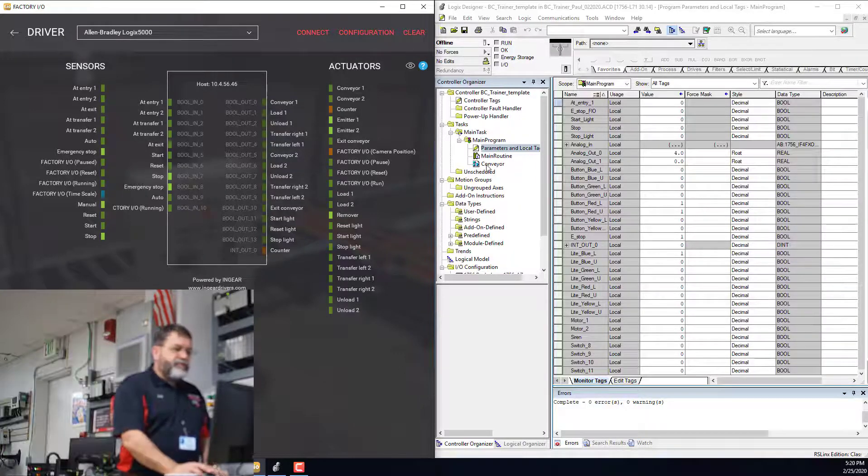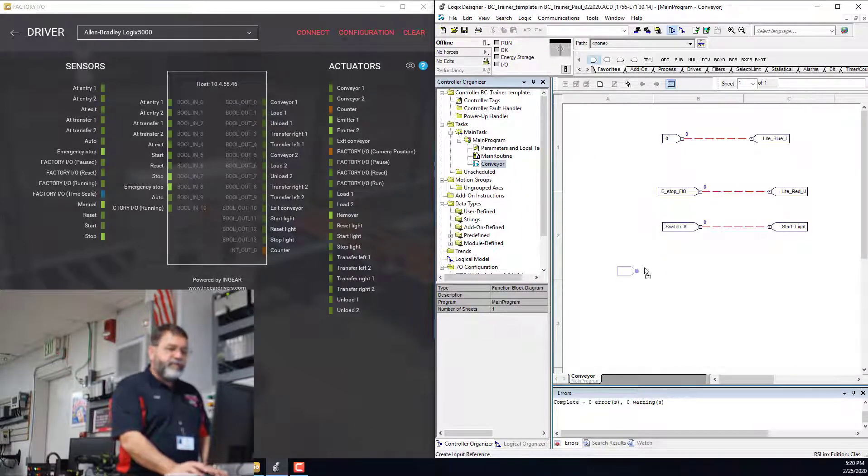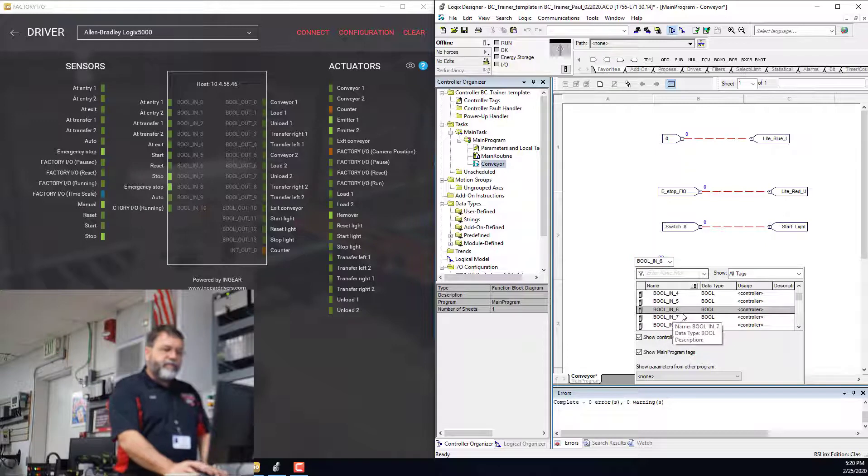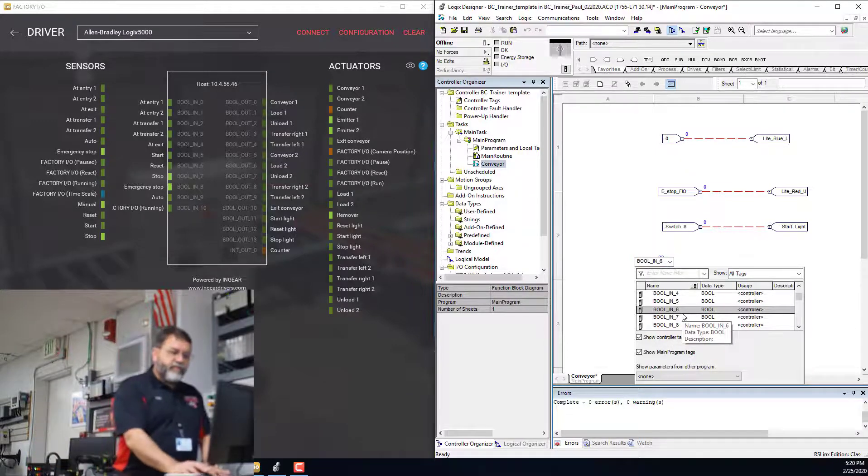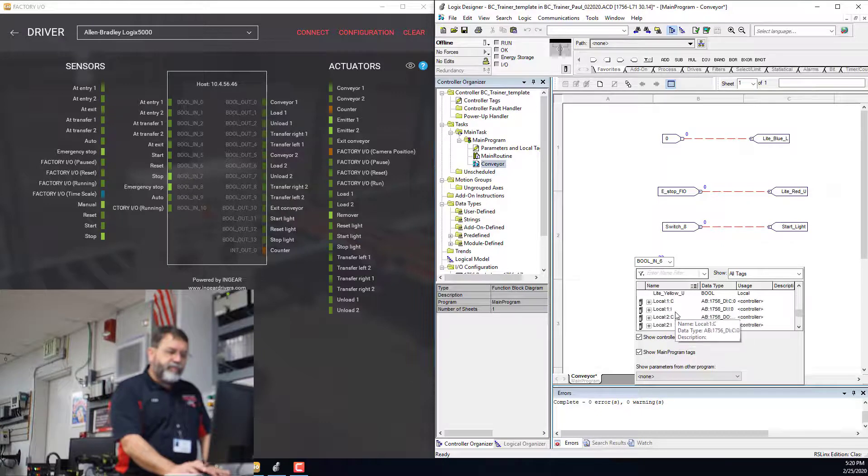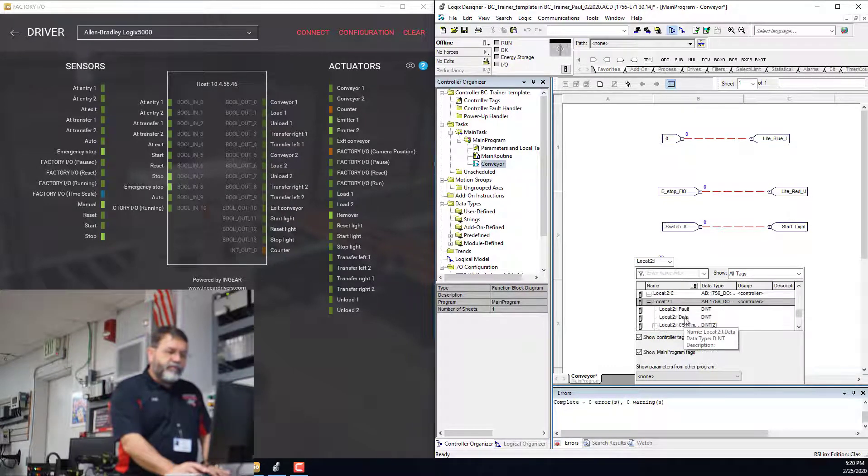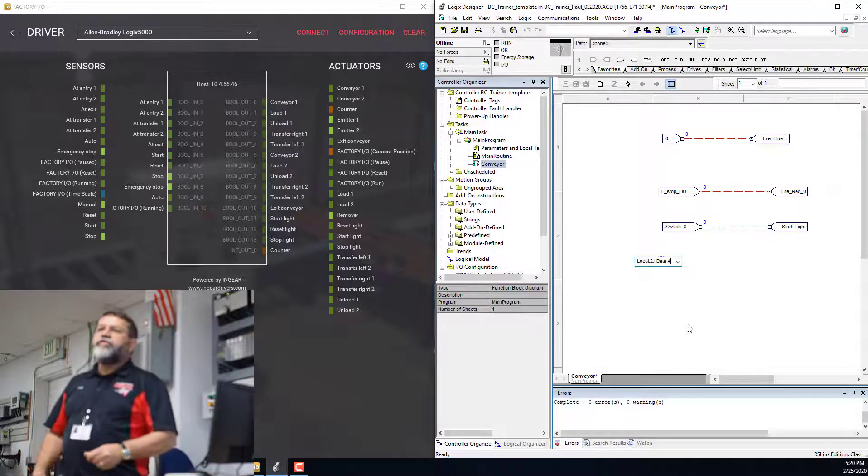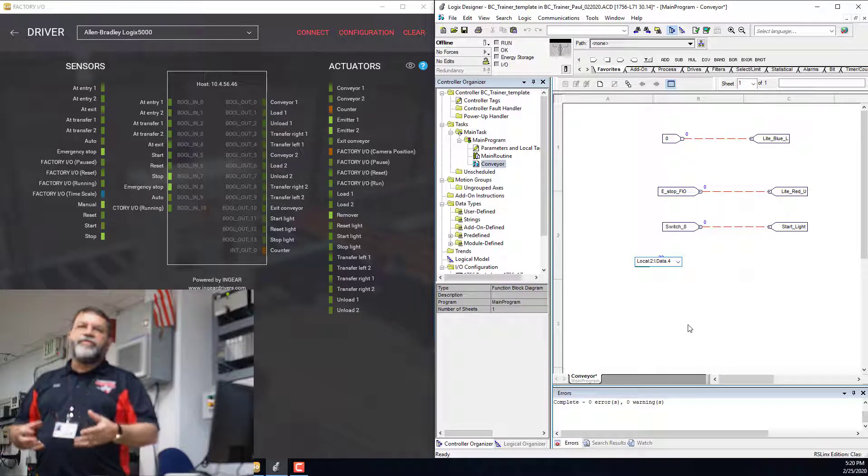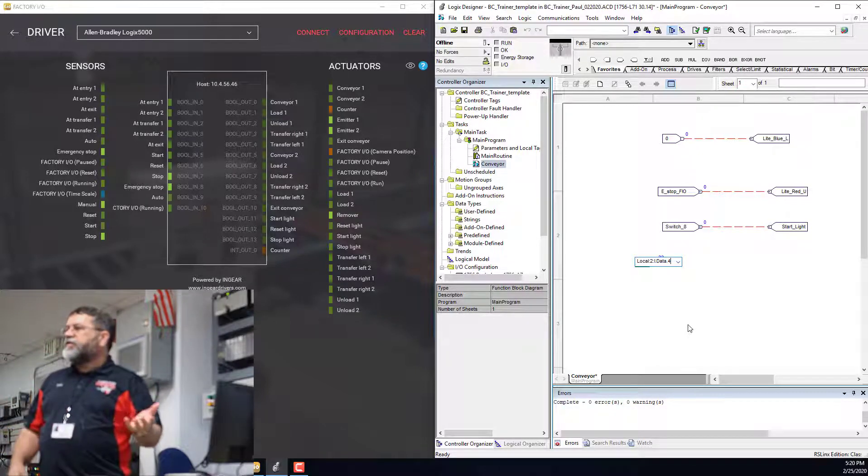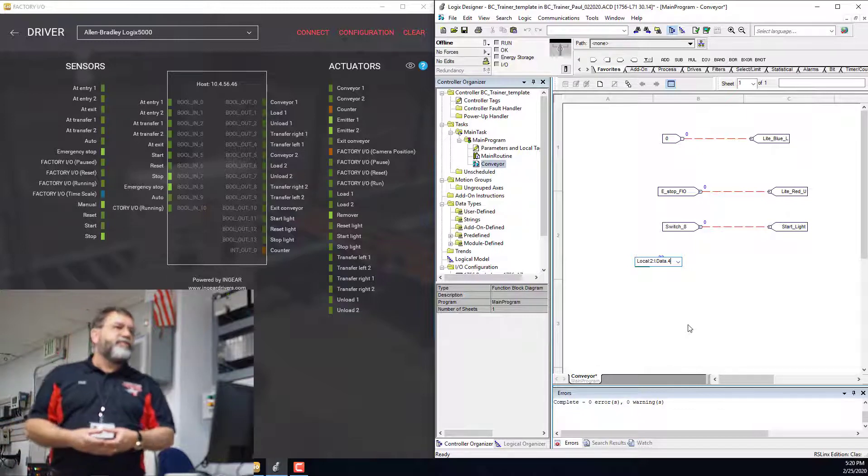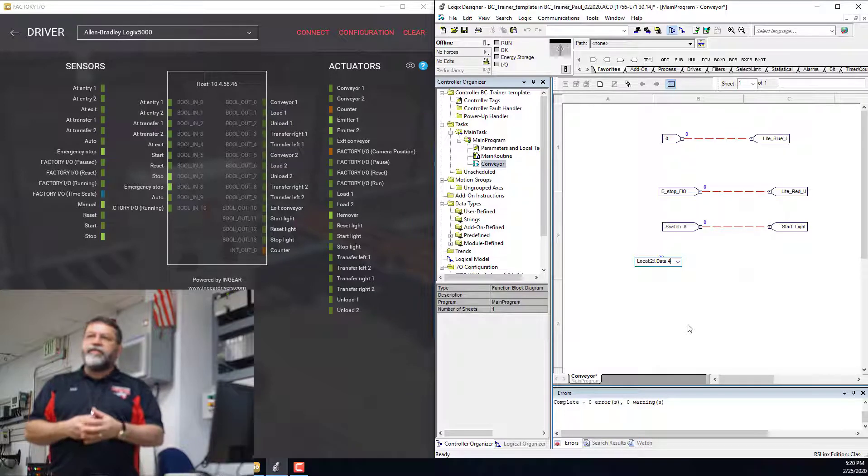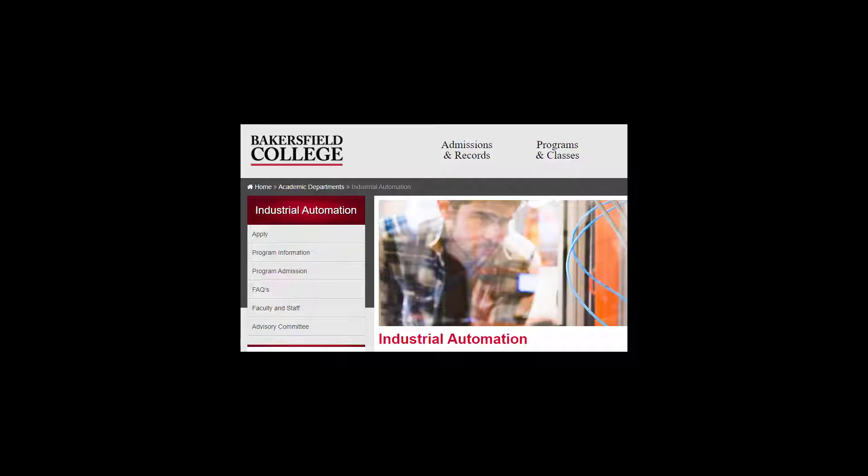When you're doing your logic, if you have, here's my input. So rather than putting in bool in six or local in data four, those types of addresses in your code don't tell you what's going on. And if you do it this way first and then go back and fix it, you're just creating a bunch of extra work. So it's better to put in all your tags, alias all your tags, and then use those when you're writing logic.